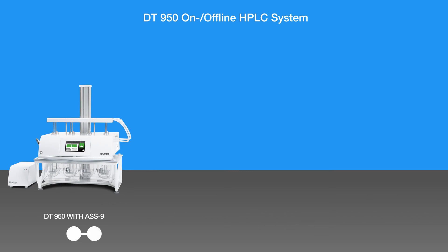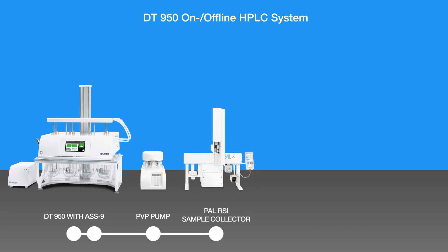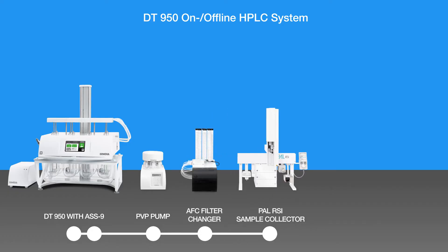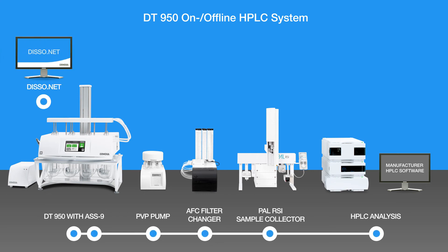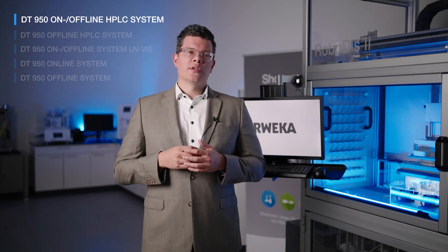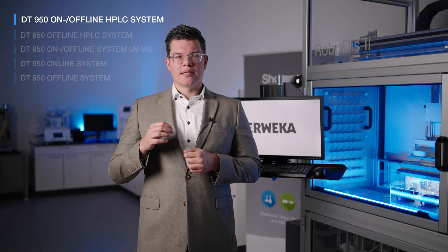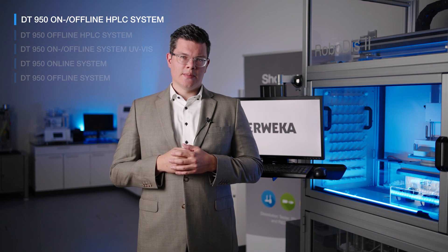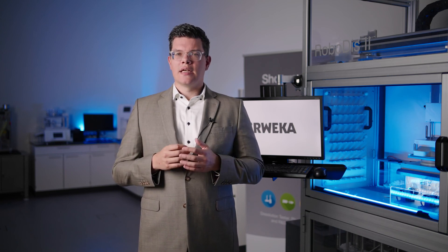A DT 950 with an automated sampling station ASS9, a PVP piston pump — which is required for optional secondary filtration — a PAL-RSI autosampler for sample collection, and the HPLC analytic system itself. HPLC often requires secondary filtration, so an automated filter changer is recommended. disso.net 4.6 controls every component up until the HPLC analysis, which gets triggered by a signal to automatically start analyzing the directly injected sample from the six-port HPLC valve, specifically engineered for our dissolution HPLC systems. This is real HPLC online automation without any gap between the dissolution test and the HPLC analysis.